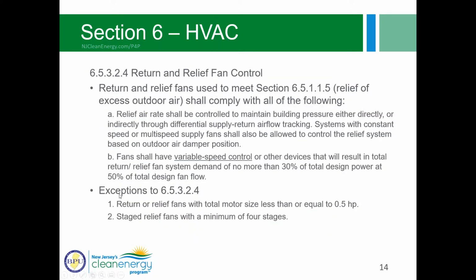All right, so section 6.5, return and relief fan control. The keys here are that the relief air rates need to maintain building pressure through differential supply-return airflow tracking and control of the relief system based on outdoor air damper position. And fans shall have variable speed control or other similar devices. The exceptions to this would be return or relief fans with a total motor size less than or equal to 0.5 hp, or staged relief fans with a minimum of 4 stages.